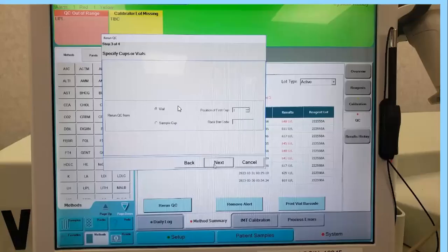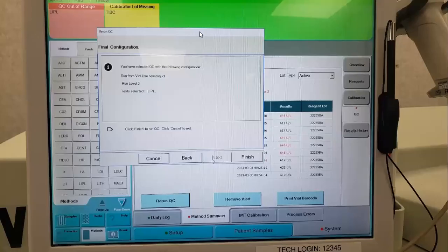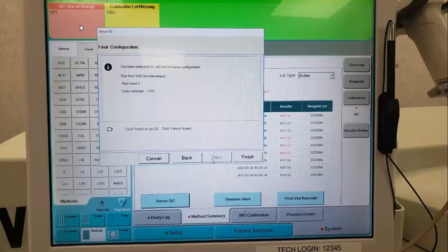Then it's going to ask if you want it in a vial or a sample cup. We're just going to keep it on vial because that is what they are loaded on the machine. We're going to click next, and it brings this up. So we're going to click next and then finish. And that will start running the QC, and it will take down that little red box here. It will take this down until it is rerun.